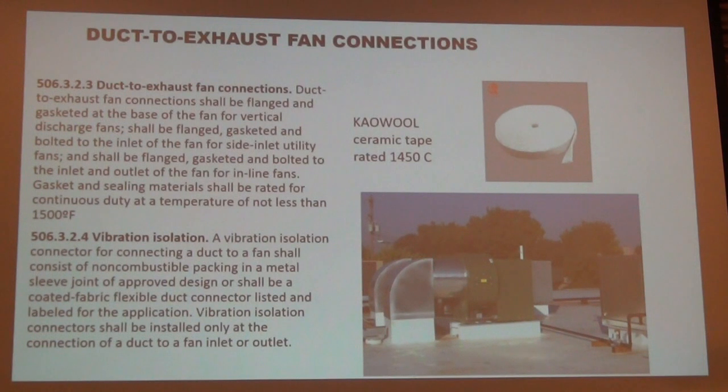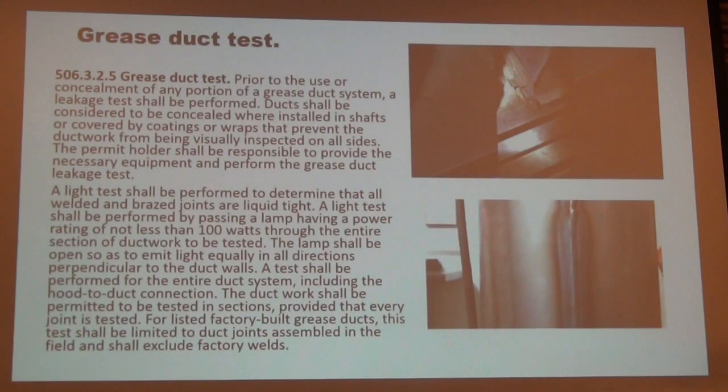If you have a vibration isolator, it consists of a metal sleeve and approved design. It shall only be installed at the connection to the duct or fan inlet or outlet. Grease duct testing, this has changed now. There's other options that you can do.